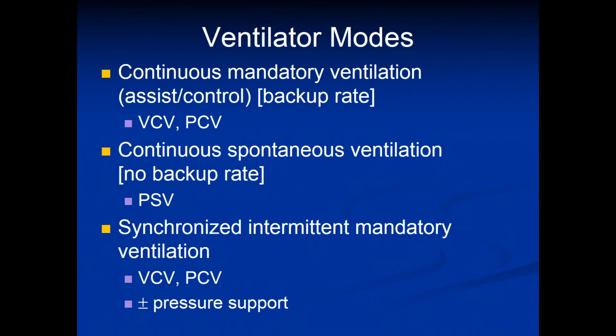In continuous spontaneous ventilation, there is no backup rate other than the apnea settings, which I mentioned previously. These breaths can basically be entirely spontaneous with no baseline pressure, or we can add a PEEP level and provide continuous positive airway pressure, and we can also institute a certain level of pressure support ventilation to supplement the patient's breaths.